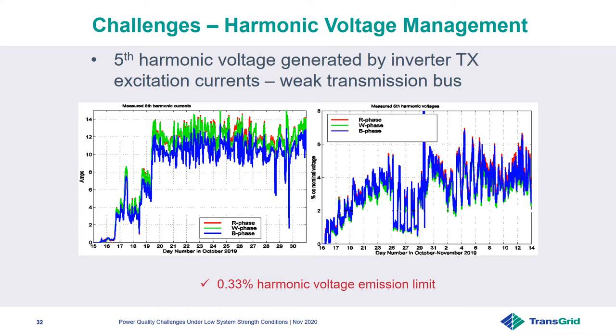Here is an example where harmonic current injected at the weak location generates very high harmonic voltage levels. In this example, approximately 10 to 14 amperes of 5th harmonic current is drawn by the inverter transformer excitation currents, and this current generates a significant amount of harmonic voltage due to the high harmonic impedance at the location. Once again, fluctuation in these measurements further demonstrates the sensitivity of harmonic impedance at this location to network events, similar to what we saw in the previous slide. To give you a context of the degree of challenge we had in this example, the harmonic voltage emission limit for this plant is only 0.33% for fifth harmonic, whereas we note up to 6 to 7% fifth harmonic being generated by the plant.